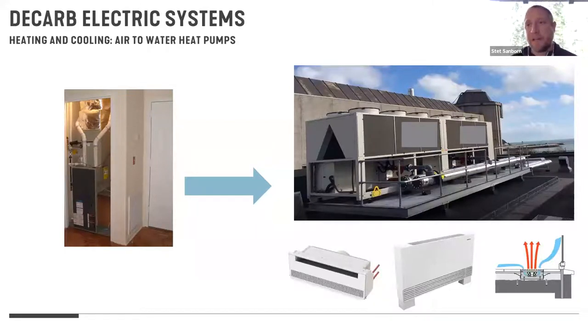And especially on the part of simultaneous heating and cooling, which a lot of our commercial clients certainly have. We have morning warm up, but we still have that core of the building or the IT closets that have significant cooling loads 24/7. And so that ability to do heat recovery provides a huge financial benefit to our clientele.